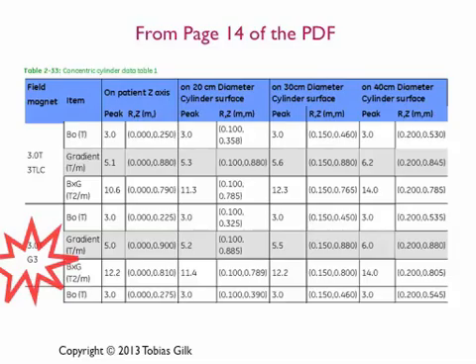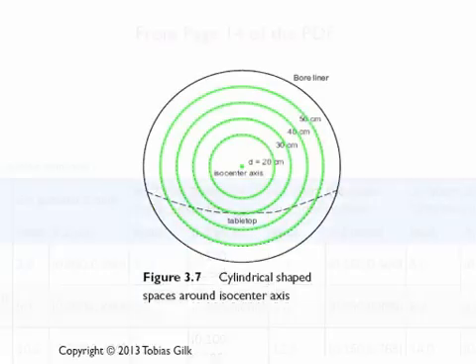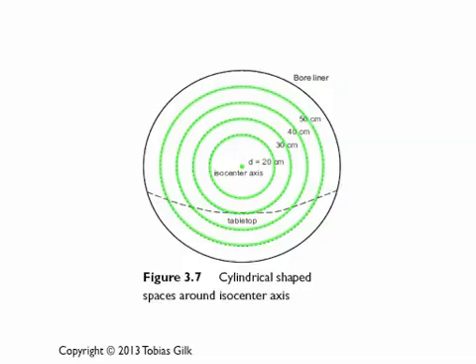The other critical thing to identify on this table is the top row: on patient Z axis, on 20-centimeter diameter cylinder surface, on a 30-centimeter diameter cylinder surface, on a 40-centimeter diameter cylinder surface. Where are all these cylinders? The cylinders are imaginary. Imagine yourself looking straight down the center of the bore, and we superimpose a bullseye of concentric rings. The Z axis is the dot in the center running down the length of the bore. As we move out at set distances — 20, 30, 40, 50 centimeters — we get these rings, which when extruded become cylinders.